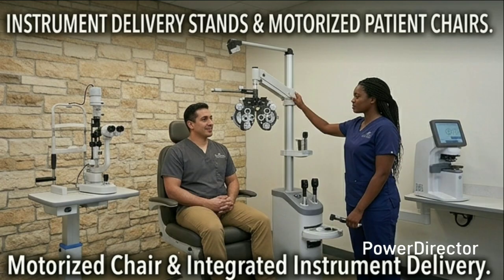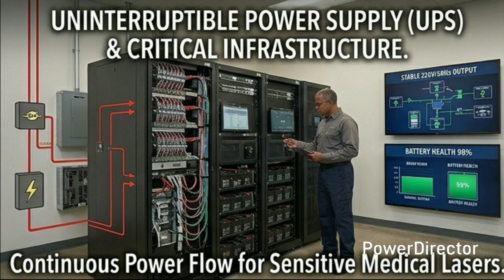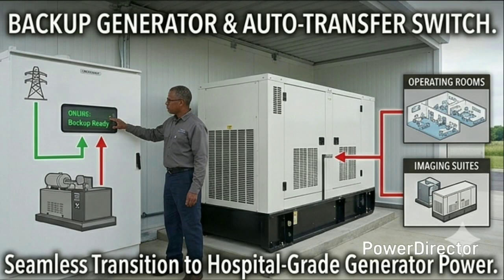Instrument delivery stands and motorized patient examination chairs. Heavy-duty, articulating chair and column units that hold the phoropter, slit lamp, and charging wells for handheld ophthalmoscopes in one seamless footprint. Uninterruptible power supply, UPS, and backup generator. Highly sensitive medical imaging and surgical lasers cannot tolerate power drops or surges. A robust backup power grid is mandatory. Moving forward, this list represents the complete physical framework of a premium, full-service facility.